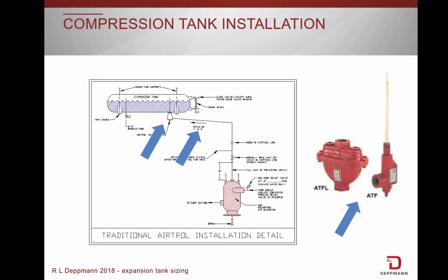When working with a system that contains a compression tank, automatic air vents can be used during the initial fill period but should be valved off after the air has been removed. Remember, this is an air control system with a compression tank.